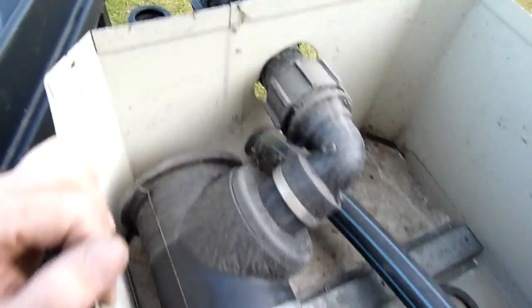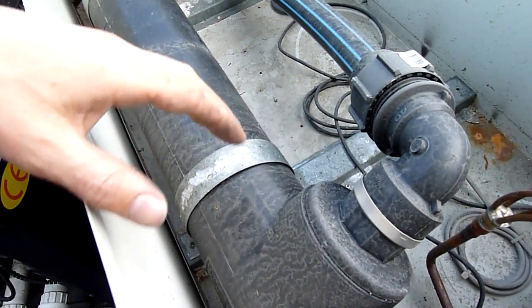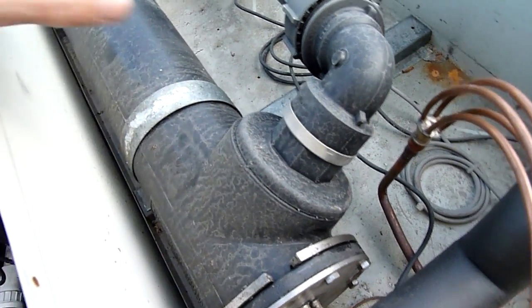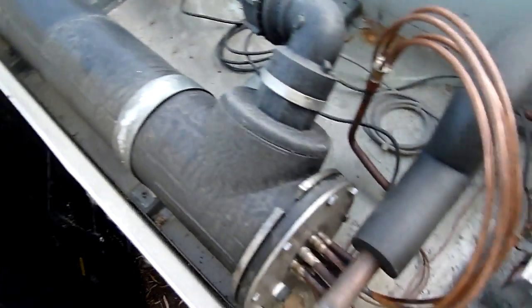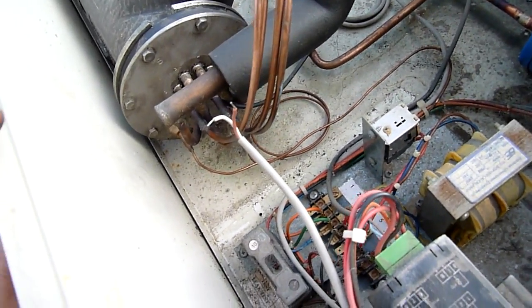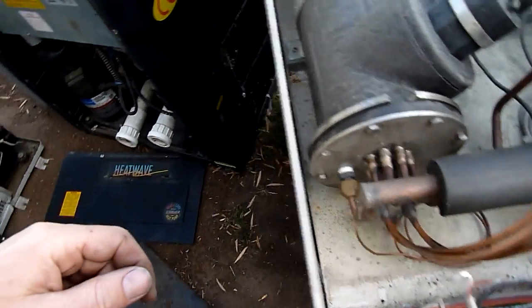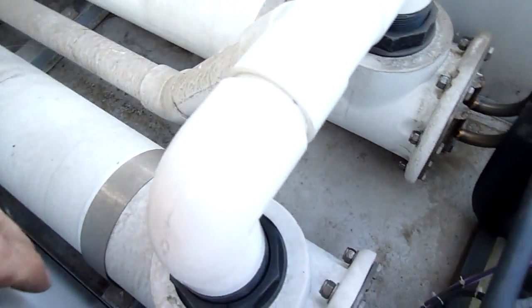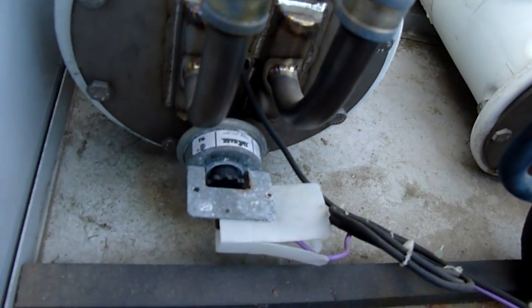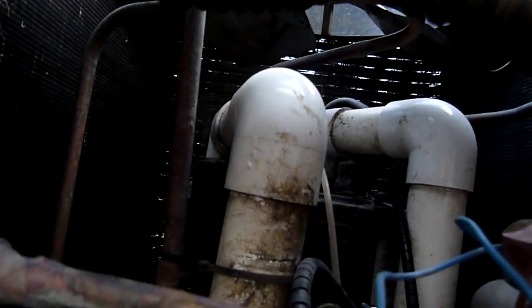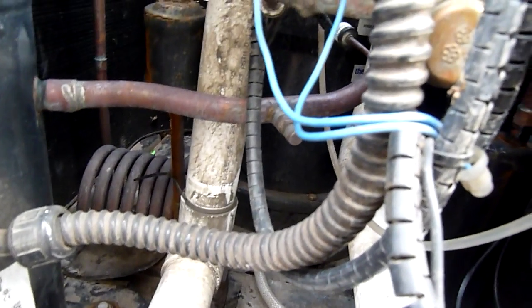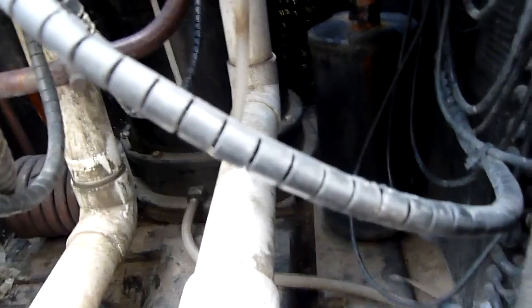I just need a pool pump and a big reservoir to chill down as a test. These should not operate with the drum full of water and the compressor running, otherwise you freeze it, rupture the heat exchanger, and it just blows up. So you must have water pressure and flow. This one has, I think, a flow switch somewhere — yeah, there, that thing is a water flow switch. If that isn't engaged, the compressor will not start and run at all. This one should have the same on top somewhere, probably that little bump in the middle. I wonder if it hasn't been run without flow — the system was always working, it just popped. So I'm curious why, but I just think it's a bad design.